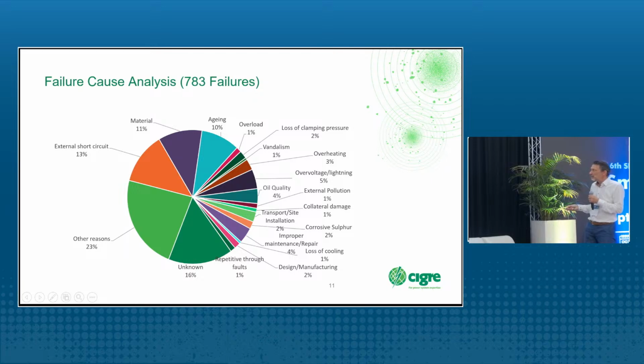Biggest contributor in this case here is external short circuits. So 13% of the failures are related to external short circuits. This is quite important information, because at the moment there is the revision of the respective IEC standard planned. In this IEC standard there is written how to check the short circuit performance, and if a lot of failures are occurring due to short circuits, you have to maybe adjust the standard a bit to improve the product.